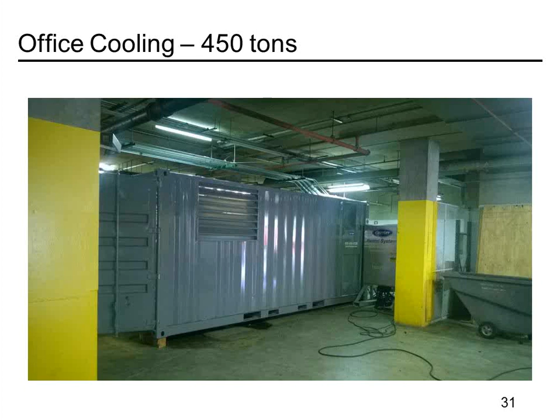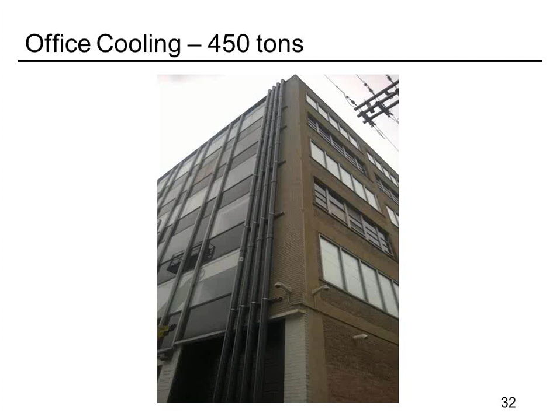Ultimately, the mechanical contractor that we partnered with on the project was able to run PVC piping up the side of the building using Unistrut to support it, and then we transitioned back into hose at the roof for both the condenser and the evaporator, after the chiller on site had failed during the peak summer months. So this was a relatively quick turnaround project. This was all completed within about a week, from the first time we were walking the site to delivering the equipment to installing all the piping and all of the work it took to get this unit up and running.